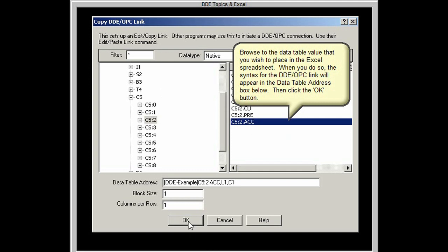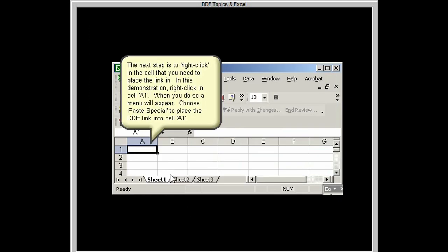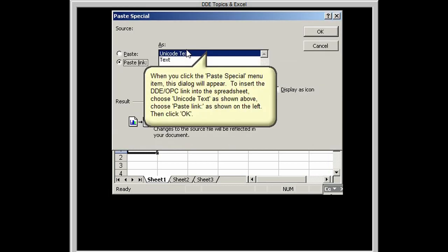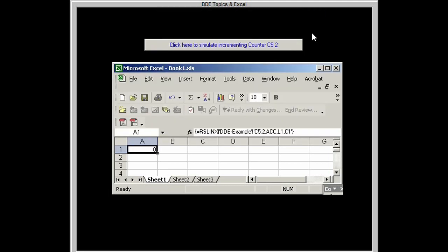There is one more format, Fast DDE. This is a proprietary format used by Wonderware. Fast DDE is faster than Excel table, but it does not perform any error checking. RSLinx is capable of using any of the formats discussed above. When a DDE channel is established, a handshaking of sorts takes place that automatically establishes the data format to be used. The fastest format that both the client and the server can use is established.